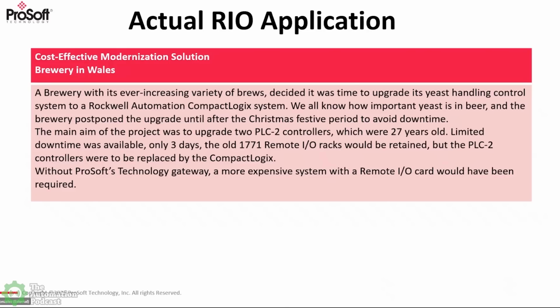The next one is our second case, a Remote IO application. Here, a brewery decided to upgrade a very old PLC2 controller to a newer Compact Logix controller, and they didn't want to replace the 1771 remote racks. One of the biggest hurdles was time, since they only had a few days to do it.